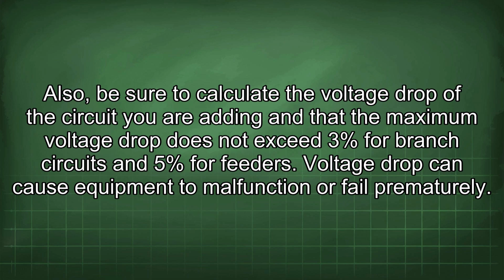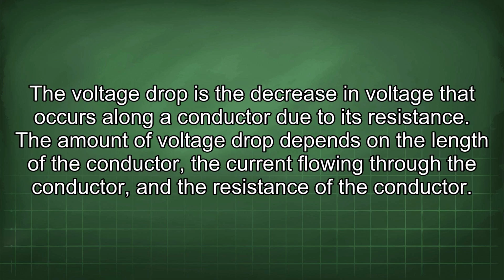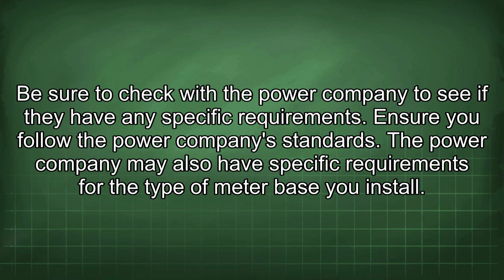Voltage drop can cause equipment to malfunction or fail prematurely. The voltage drop is the decrease in voltage that occurs along a conductor due to its resistance. The amount of voltage drop depends on the length of the conductor, the current flowing through the conductor, and the resistance of the conductor. Be sure to check with the power company to see if they have any specific requirements. Ensure you follow the power company's standards.